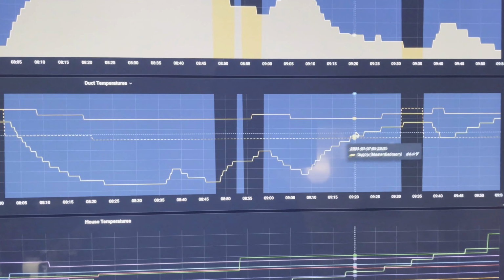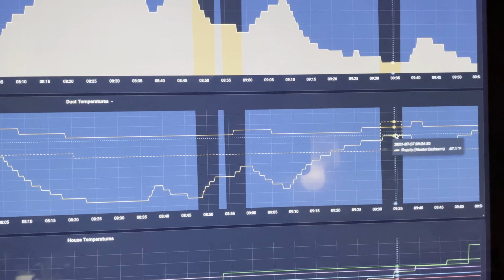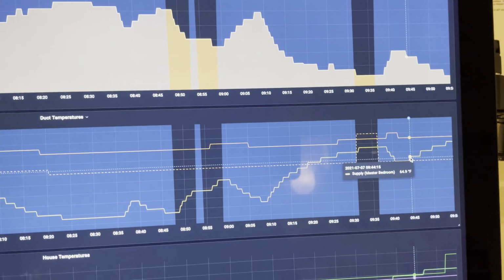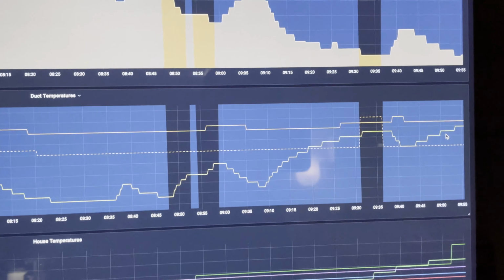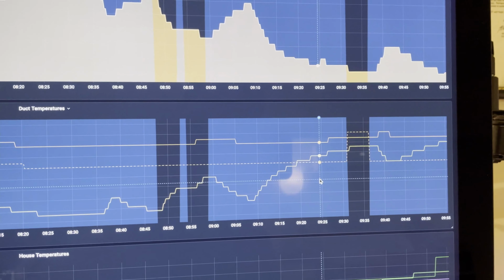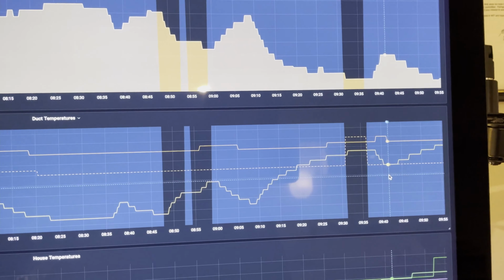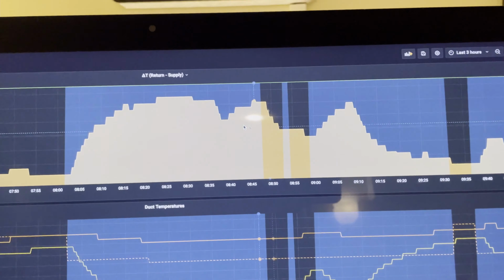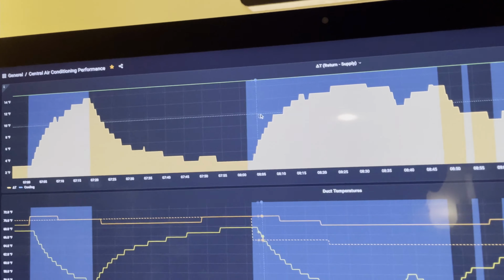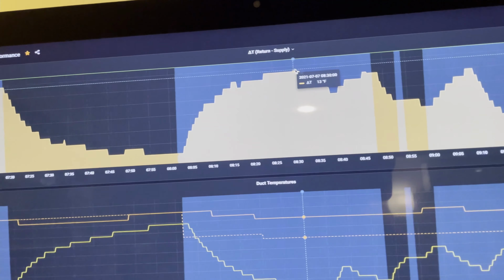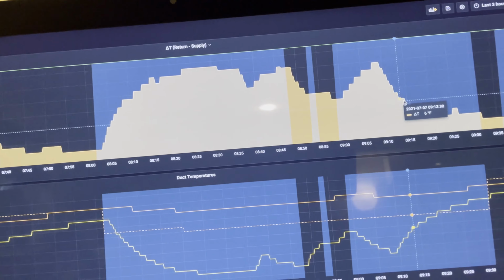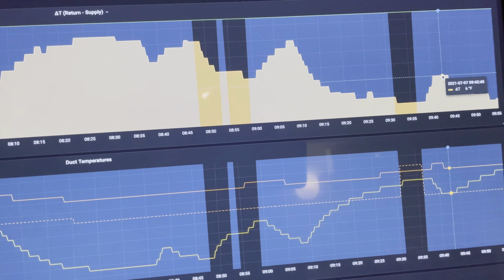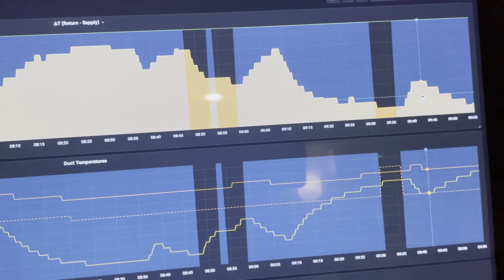It's cooling for a while, and then the temperature rises. And then normally this doesn't happen because I don't mess with the thermostat. Just after a while, it'll reset on its own, I guess, because the compressor cools down and the thermal overload resets, and then it starts to cool again a little bit, and then it goes off again, then it cools a little bit, then it goes off again. And meanwhile, I see my delta T graphs up here, which shows me how much cooling I'm getting, normally around 13, 14 degrees. Throughout those hot days, I get less and less and less until I'm only cooling like 4, 5, or 6 degrees. So that is exactly what I'm seeing, and it's starting again today.